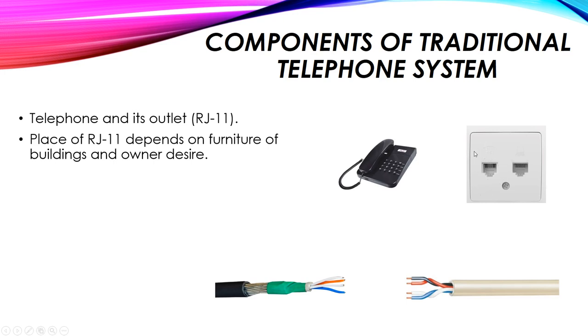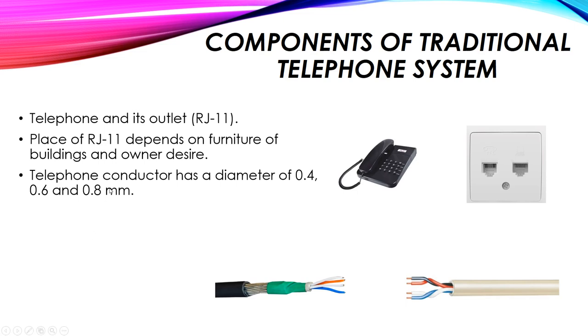The placement of the RJ11 telephone outlet depends on the furniture of the building and the owner's design. For example, in an office, the outlet should be placed next to each desk where a telephone exists. In our home, we can have more than one telephone on one line, using as many telephones as desired. The telephone conductor itself can have different diameters — 0.4, 0.6, or 0.8 millimeter — with 0.6 millimeter being the one most frequently used.